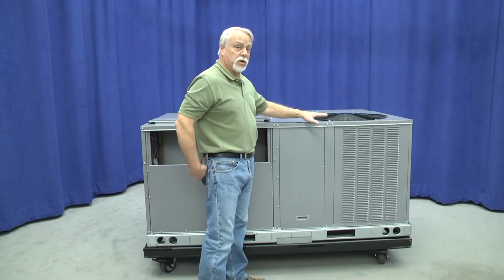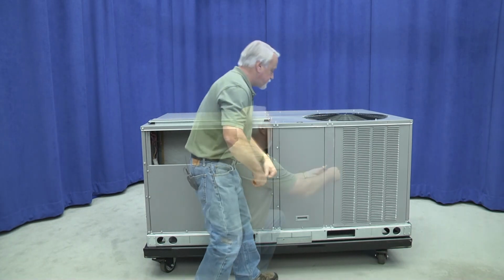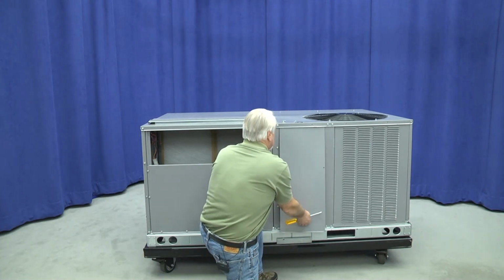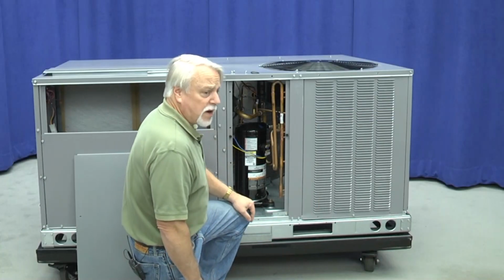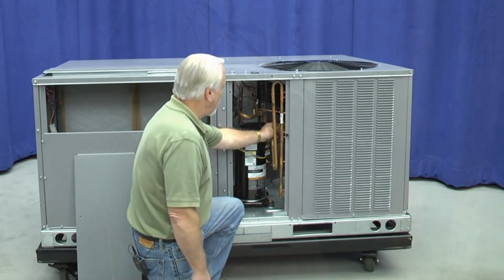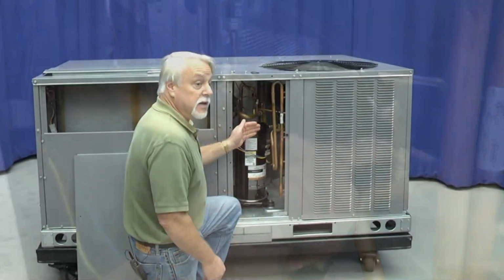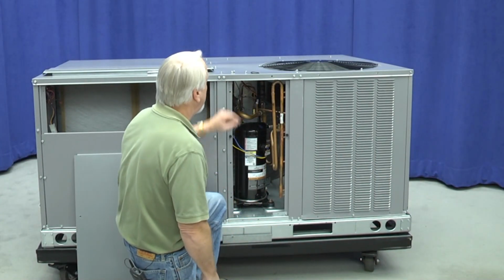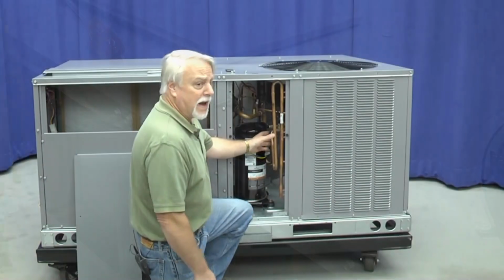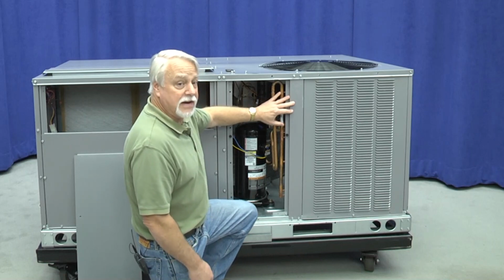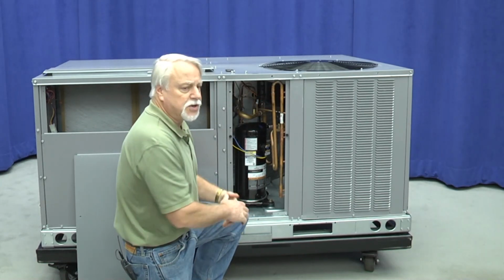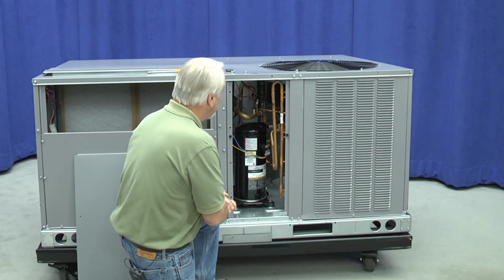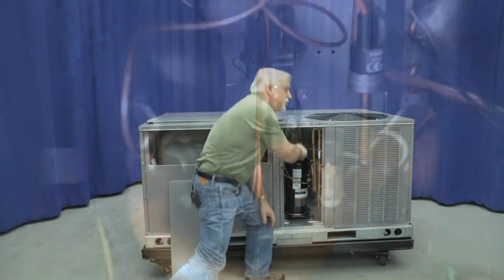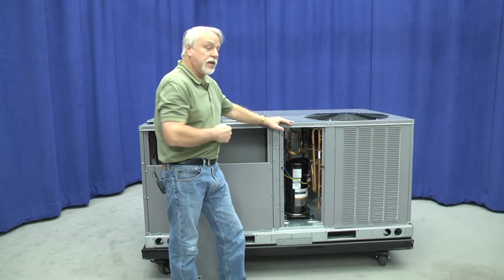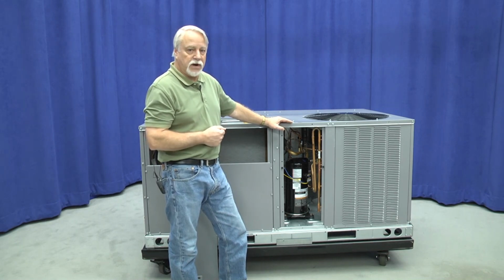Moving down this side of the machine, we're going to look at the compressor access opening on the unit. With the compressor access panel removed, I can see connections up here for both my high side and my low side pressure, as well as liquid connections so I can check my refrigerant side pressure drop. By removing this plug in the top of the unit, I can route my gauge lines out through the top, replace the panel, and then I prevent any bypass air over the condenser so I get a truer reading of how the refrigeration system is working. Notice this particular unit has a TXV type refrigerant control system. Follow the charging table or charging chart that is on the panel on that particular machine to confirm that I've got the right refrigerant charge.